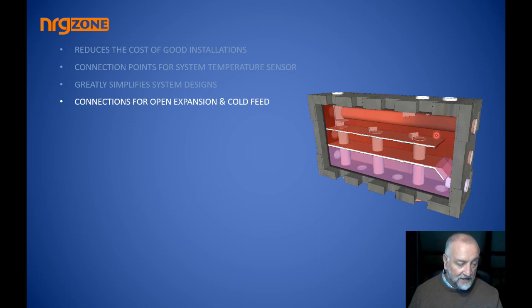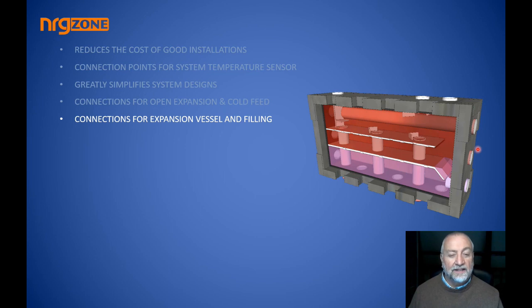And then if I go to my connections for cold feed and expansion, again, there are very logical reasons why they would be connected to where they should be, precisely connected with every system. The expansion and filling points are also likewise just what I described. They're perfectly placed onto the system neutral point.